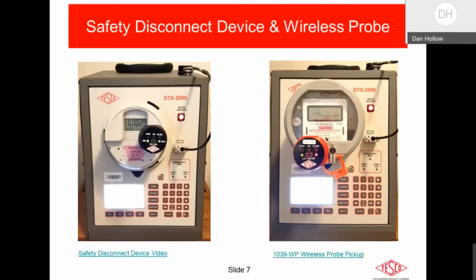But when I try to apply that rationale to it, it's such an insignificant amount of money for a metal plate. I really can't justify the decisions that some meter manufacturers made to eliminate that metal plate and just put that plastic ridge on the front of the meter, knowing that you had no way to connect an optical pickup or an optical probe that has a magnet in the head to adhere to it. So I don't have a good answer as to why some meter manufacturers chose to go that route, or for that matter, why some meter manufacturers that have optical probes on their meter, they have the optical port on the meter, but yet their infrared test pulse LED is at 12 o'clock or 9 o'clock or 3 o'clock.